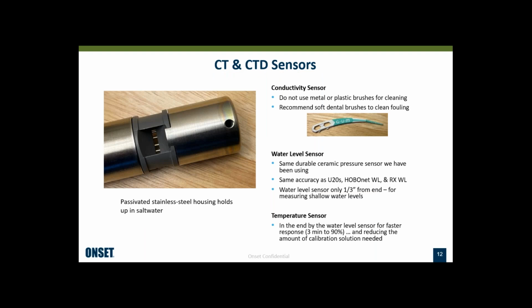Some more details about the conductivity sensors. They should not be cleaned with any metal or plastic brush. We recommend the soft dental brushes like the one I've pictured here, which has kind of rubber tines on it that are very gentle on the electrodes, but good. They are able to take off a lot of the fouling. The water level sensor in here is in the end unit, very close to where you see the hole in the end there. It's the same durable ceramic sensors that we've been using in our U20 and HOBOnet water level sensors. So it's very well proven.